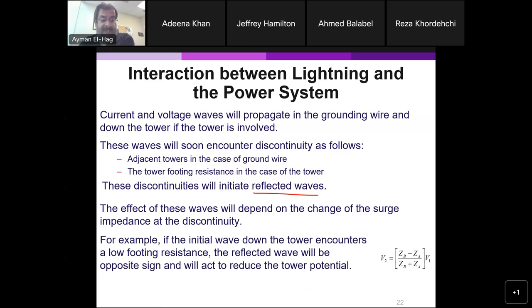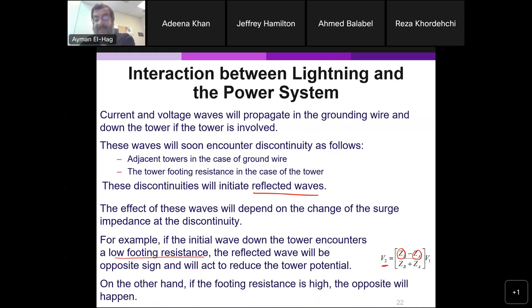Now, what is the impact of this? For example, if the initial wave down the tower encounters a low footing resistance, which is what we want, why do we want that? Because ZB is the impedance of the foot resistance, and ZA is the total impedance encountered by the surge. If ZA is higher than ZB, your V2 will be negative, and this will reduce the surge that goes through the tower, which is a good thing. If you have a bad foot resistance, V2, the reflected wave, will be positive, so it will be added to the strike wave, and that is really bad.